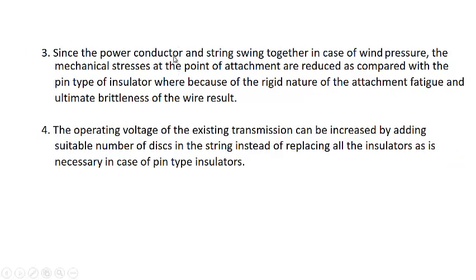Since the power conductor and the string swing together in case of wind pressure, the mechanical stress at the point of attachment is reduced as compared with the pin type insulator, where because of the rigid nature, attachment fatigue and ultimate brittleness of the wire result.